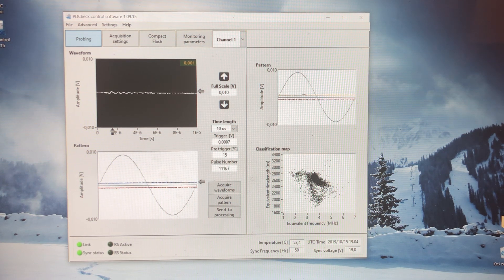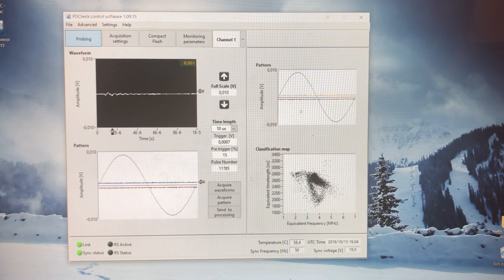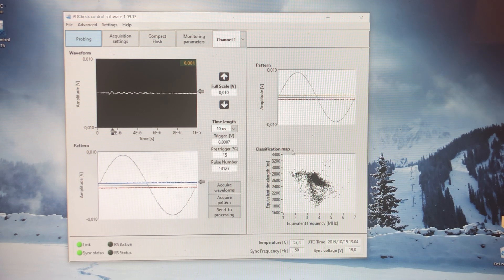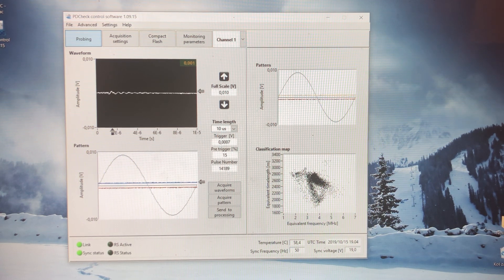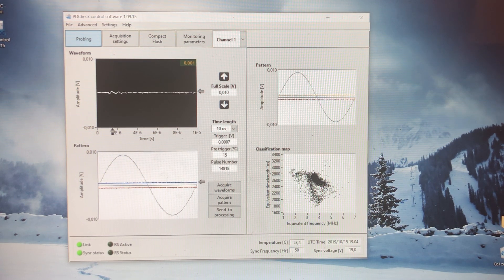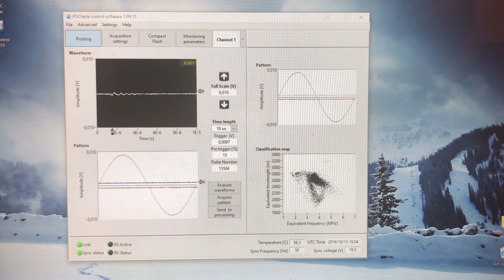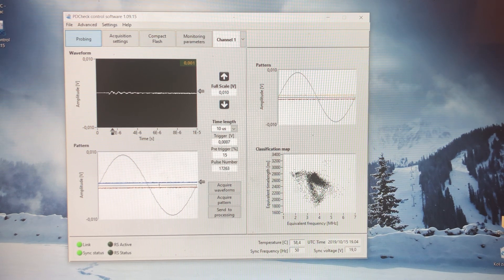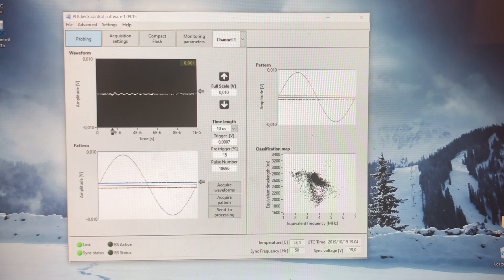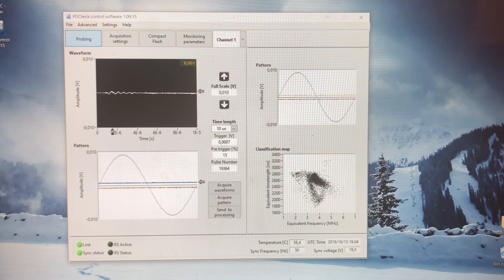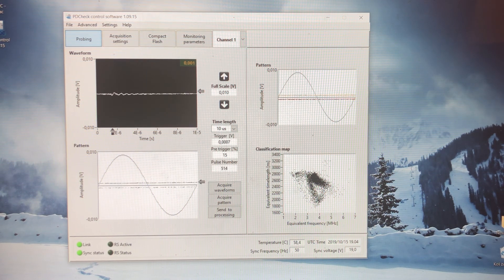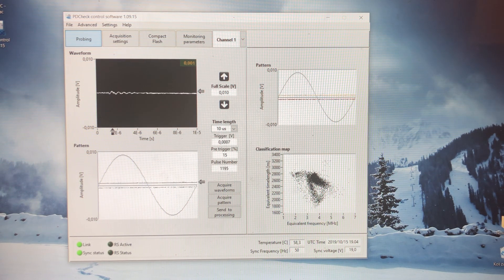This is the so-called PRPD pattern, which is copied here. Then we do an analysis and create a classification map called a TF map. This TF map puts every point from the time domain here into a frequency domain, which is represented here.